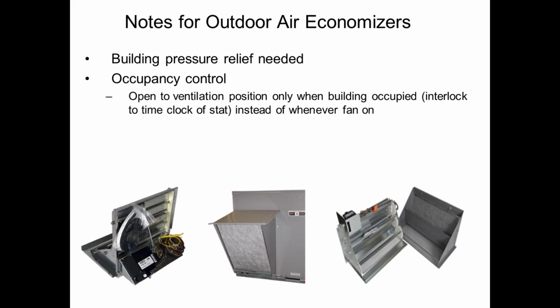The ventilation codes do not require us to ventilate when no one's there. And the energy code actually tells us we're not supposed to do it, right? So the energy code says that whenever the building's unoccupied, I have to schedule the dampers to go fully closed, regardless of where my outside air dampers are. In this case, my economizer is my outside air damper, so my thermostat has to tell, or somebody has to tell my damper, go closed at night when no one's there, or go closed whenever no one's there.